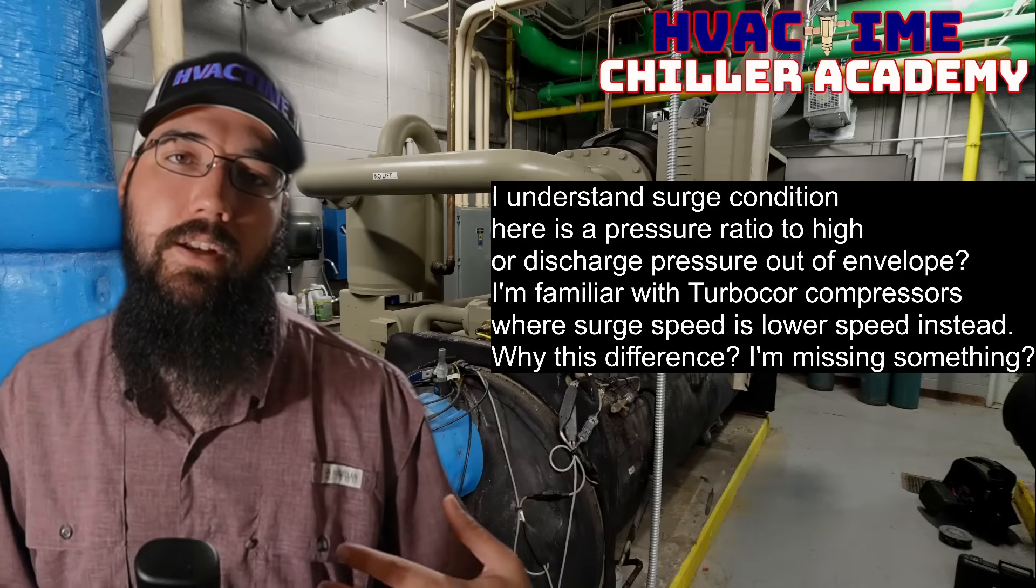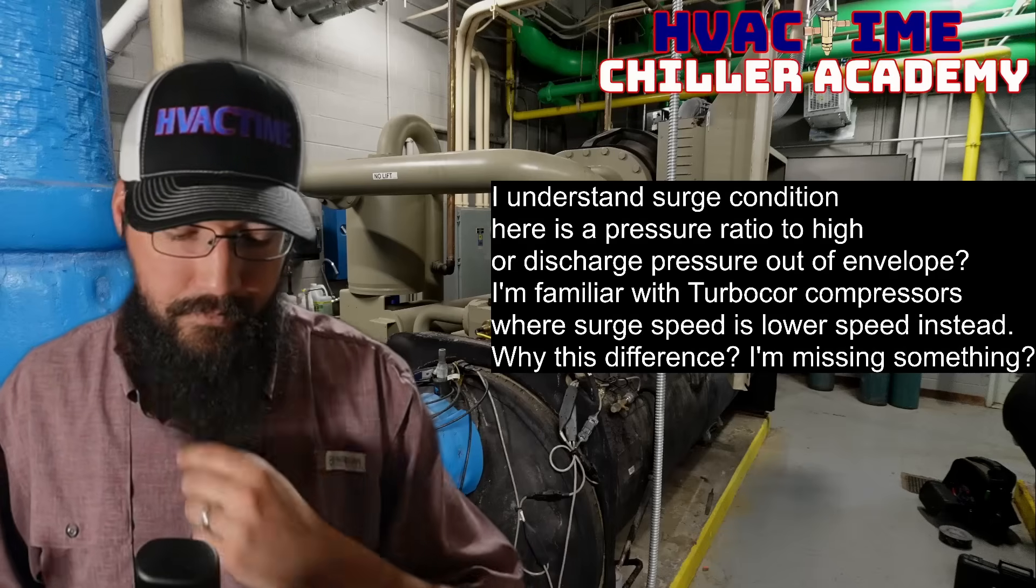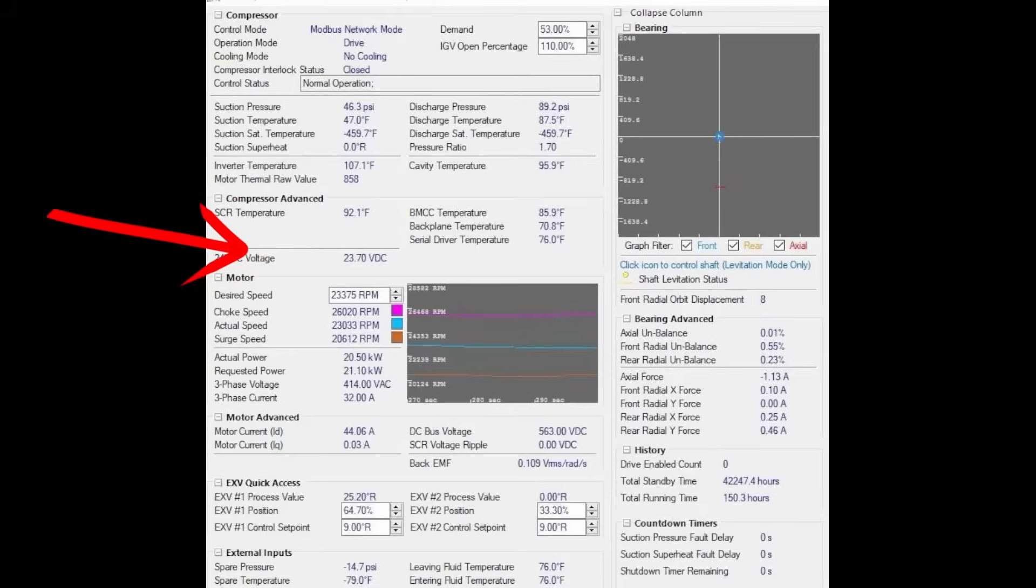In other graphs you can see it as actual speed. Let's pull up an actual Turbocor. This is the SMT tool from Turbocor, and what's being referenced here is the choke speed actual and surge speed. You'll notice the surge speed is lower than the choke speed.